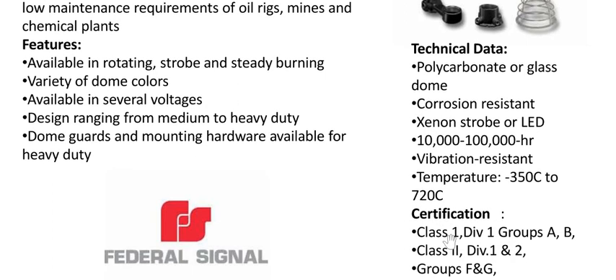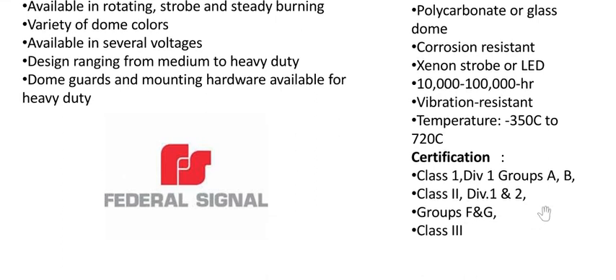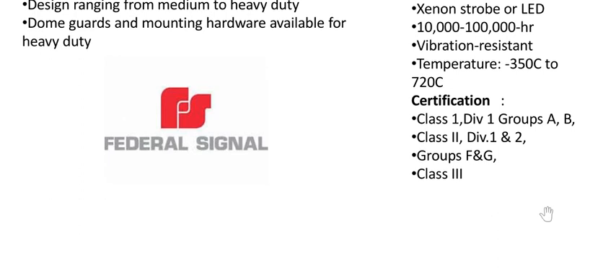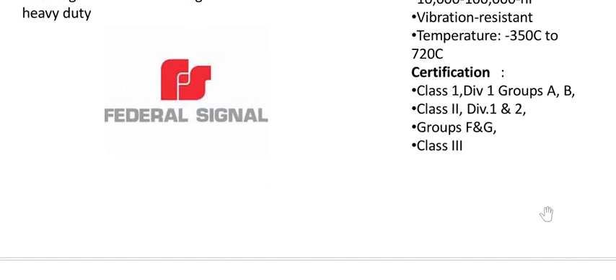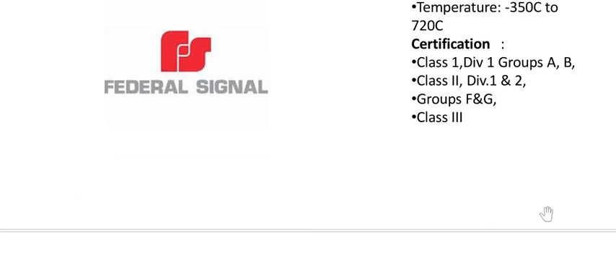The technical data: polycarbonate or glass dome, corrosion resistance, xenon strobe or LED, 10,000 to 100,000 hours, vibration resistant. Temperature is minus 35 degrees Celsius to 72 degrees Celsius. Certification is Class 1 Div 1, Group A and B, Class 2 Div 1 and 2, Group F and G, Class 3.